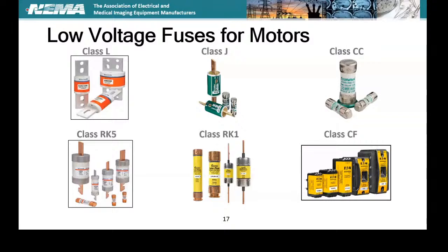Now we have a note here. Actually, this is a question. You're all going to have to write a question down, and we're going to go through some of these things, and you're going to have to come up with an answer at the end if you want your CEUs. What is the only UL fuse class to have ampere ratings up to 6,000 amperes? What is the maximum defined ampere rating of a Class CC fuse? What is the difference between a Class R fuse and a Class K fuse? And what fuse line is renewable?